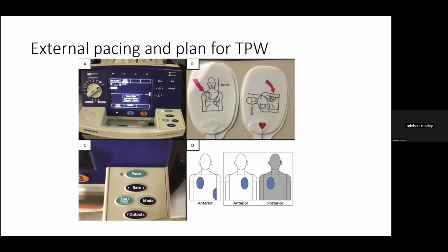Then what you've got to do is you turn the output up to maximum energy. You increase the rate to the rate that you want the external pacing to kick in at and to pace at. You press the mode, which should be for demand pacing, so that if the heart's doing its normal thing, the external pacing won't, and it will only intervene when the heart's trying to go too slowly. And you press the start button. And what you see then is when there is external pacing, you see the patient jolting up and down, and hopefully you have a conscious patient.